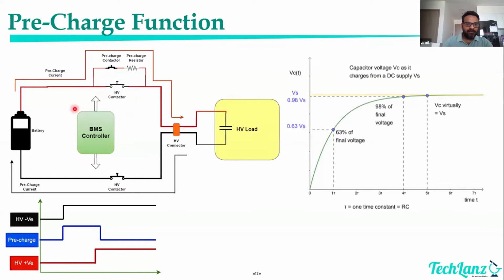Now let's see how pre-charge works. Before turning on the HV positive and HV negative contactor directly, we allow this capacitor to charge slowly, so that during HV turn-on we don't get a high inrush current. So what we do is create a pre-charge section, with a pre-charge relay and a pre-charge resistor. Before turning on the HV positive contactor, we turn on the pre-charge contactor. During pre-charge, current flows from the battery, out through the pre-charge contactor, through the resistor, and into the load. From the load it goes out through the negative contactor back to the battery. Because of this resistive element and the capacitor we're trying to pre-charge before turning on HV, we call this pre-charge.